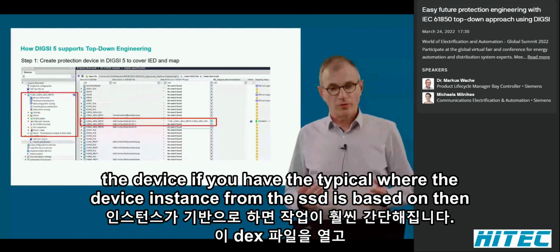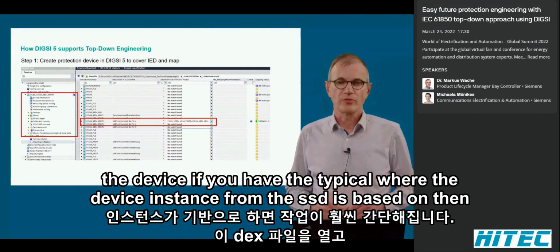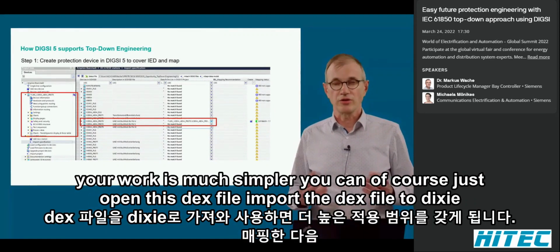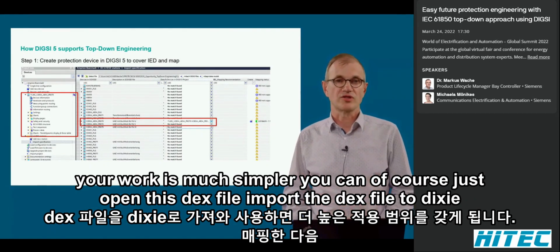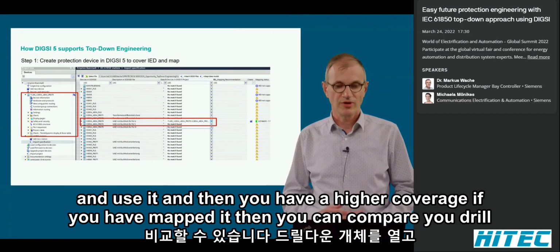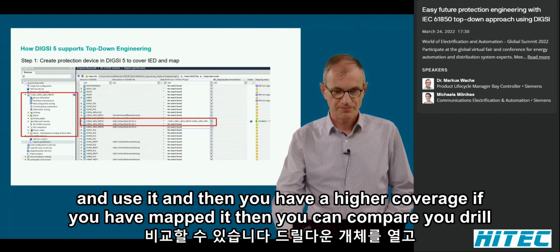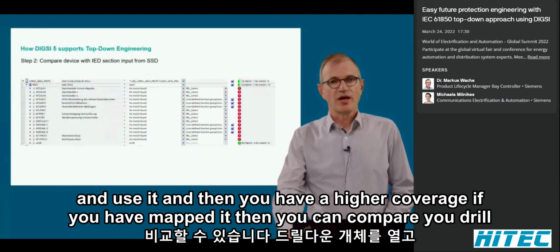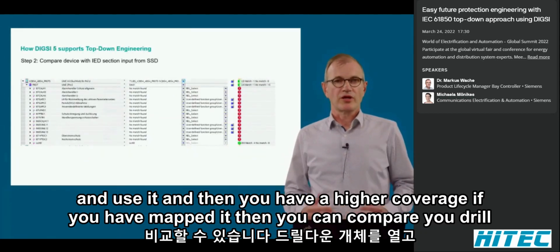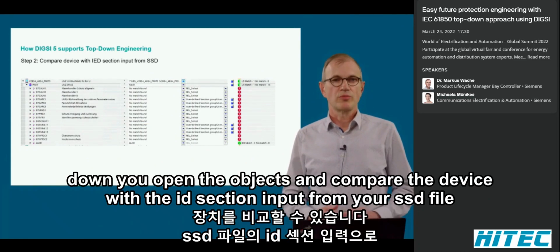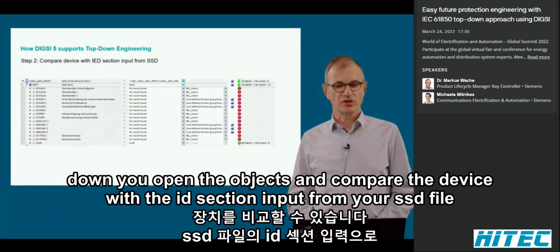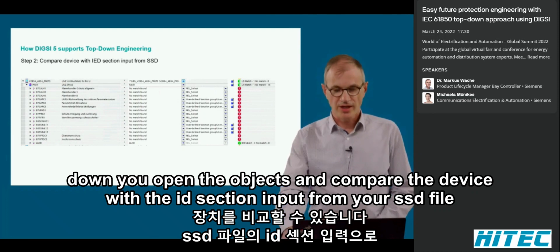If you have the typical, where the device instance from the SSD is based on, then your work is much simpler. You can, of course, just open this DEX file, import the DEX file to DIGSI and use it, and then you have a higher coverage. If you have mapped it, then you can compare. You drill down, you open the objects and compare the device with the IED section input from your SSD file.